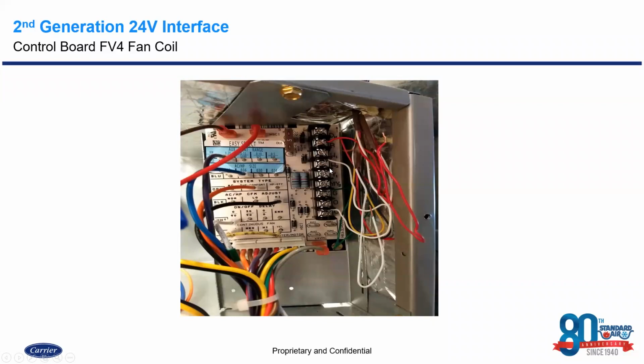Now that's one thing that we didn't talk about. W2 terminal on here is that if we have auxiliary heat, which most of the time we typically do, what we want to do is we want to set these thermostats as a 2 heat, 1 cool option. So Y1 would be bring on the AC, W1 would be bring on the heat pump, and W2 would bring on the electric heat, and it would send that control signal directly to this W2 terminal from the thermostat.